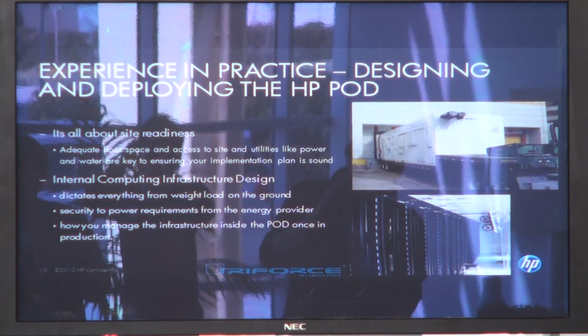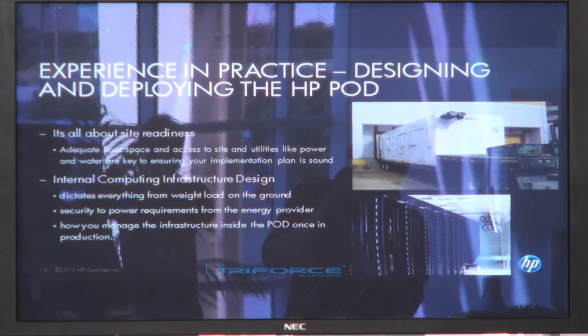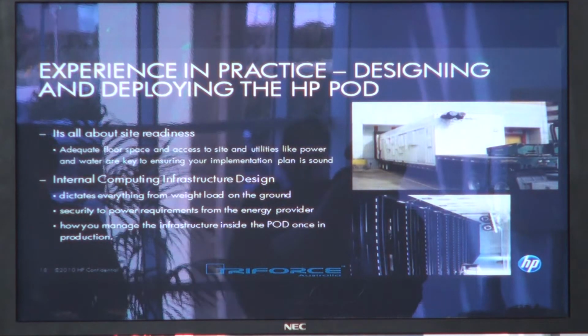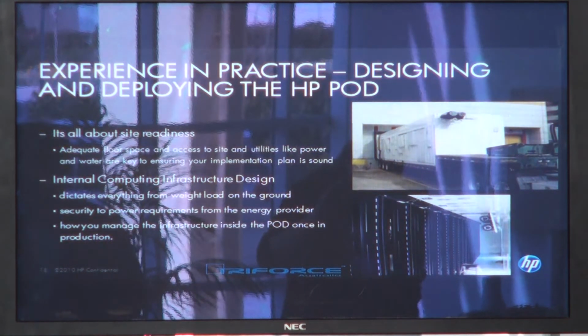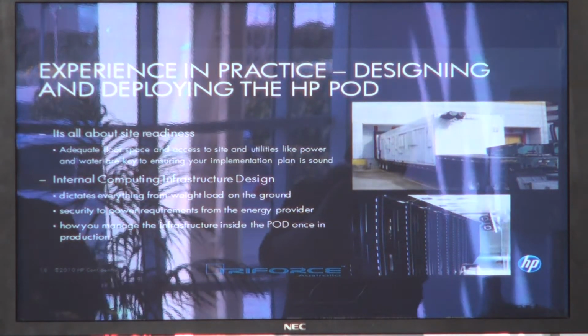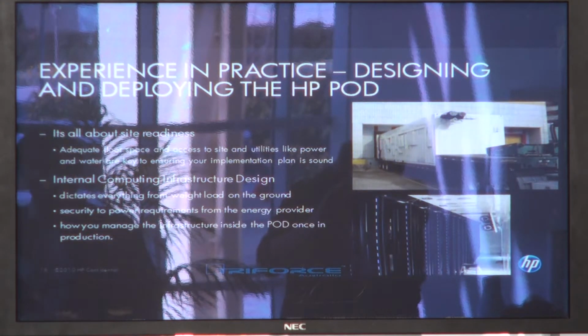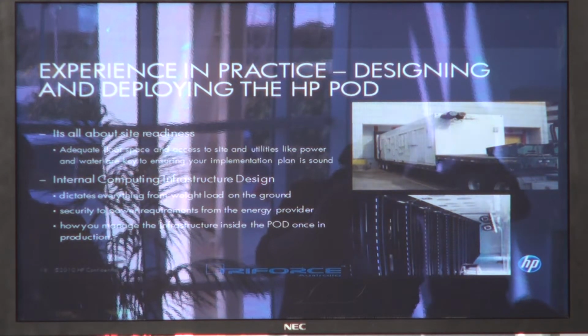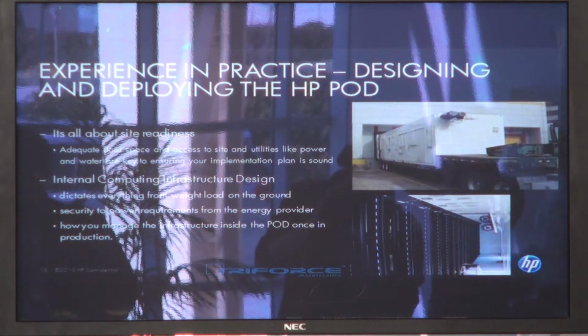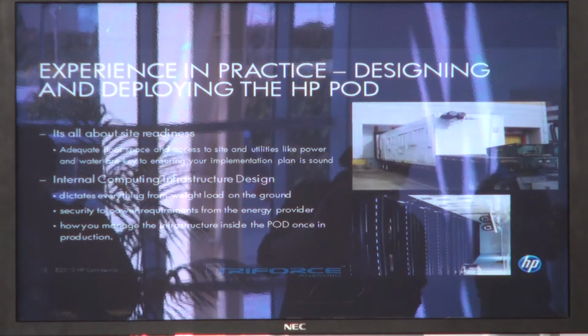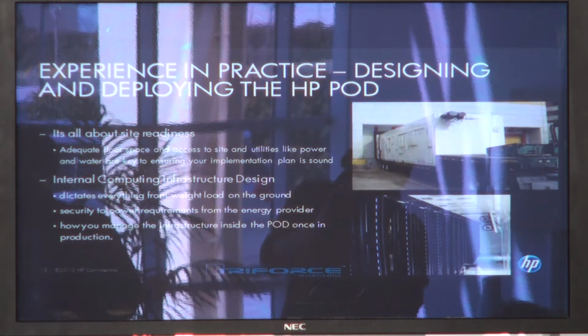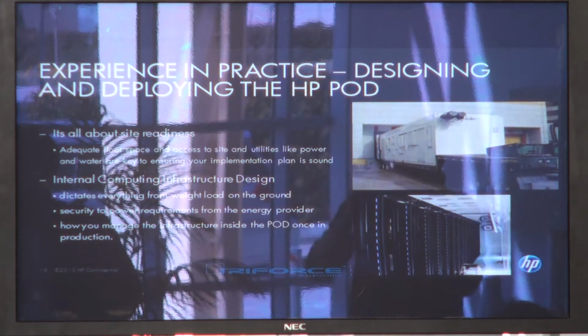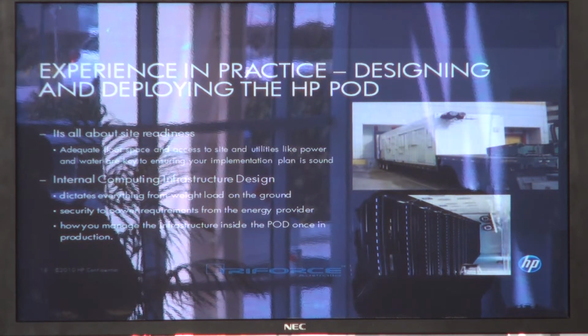I'll give you a rough figure. A lot of the Tier 3 data centers in Australia generally don't allow you to put more than one HP blade chassis per rack, and that's for two or three reasons: power, cooling, and weight. Some HP blade chassis can fit 32 servers in a space about this size, 10 RU, and they can weigh up to 200 kilos. So you start to run into some things you need to consider when putting in an HP pod.